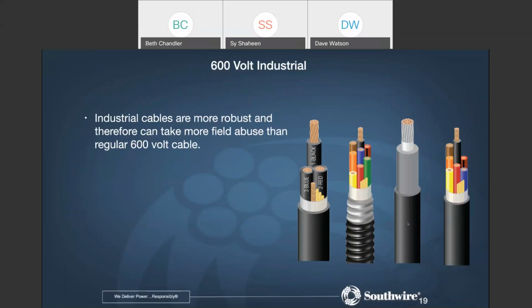This would equate to, for instance, THHN. Well, this would take the place of THHN. My goodness, it has an insulation and then a jacket. This is the most rugged one out there. It's still rated 600 volt, and then we finally have the tray cable multi-conductor control with an overall jacket. So the point here is, if you want ruggedness, then you would have to go to the industrial type cables. Whereas if you want something a little bit more economical and you want to save money, obviously you would use some of Dave's products.